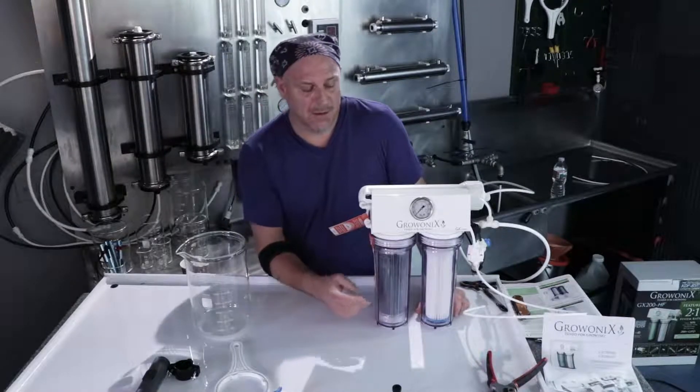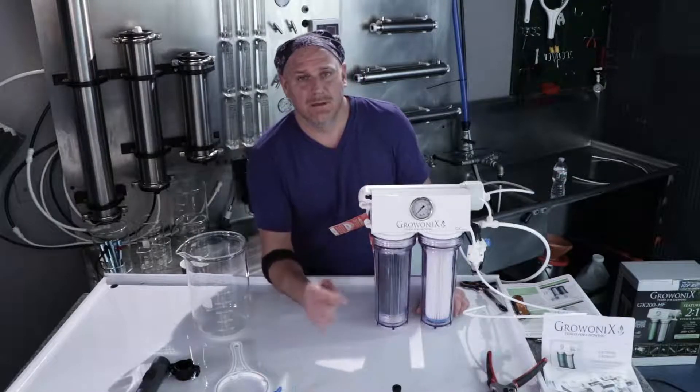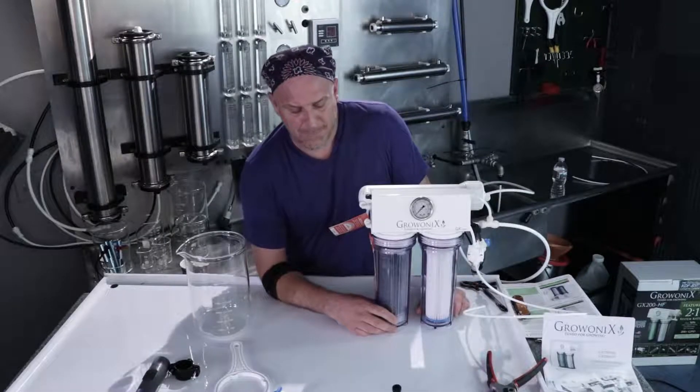KDF filters are really dusty, and you don't want that carbon dust going into a brand new membrane. You will ruin the membrane, so we have to flush the KDF carbon filter.